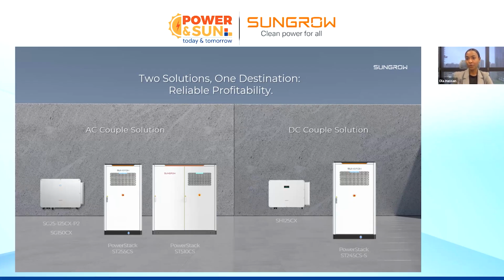On the other side, the new addition is the DC coupled solution. So now we have a hybrid inverter with a capacity of 125 kilowatt. This hybrid inverter has two outputs: AC output on grid and AC output as an emergency port. We can connect this also with the Power Stack series, but this Power Stack series will be different. It will not have a PCS because the inverter is already hybrid. So it does have the features of power conversion and charging and discharging the battery.